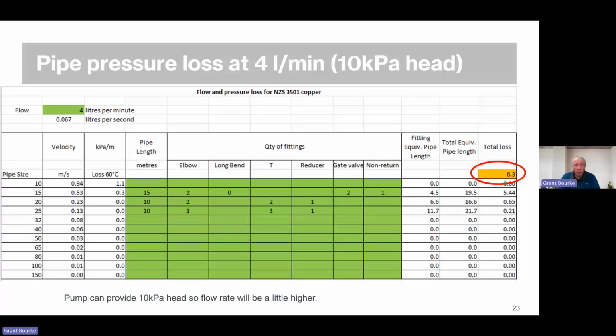Now, our pump at 4 litres a minute is going to run 10 kPa of head. So what it means is the pump's going to increase its flow rate until the pipe and pump pressure loss and flow rates are balanced. So that's our first iteration. We weren't far off, but we need to increase that flow rate a little bit so we get those flow rates of pump and pipe balanced.